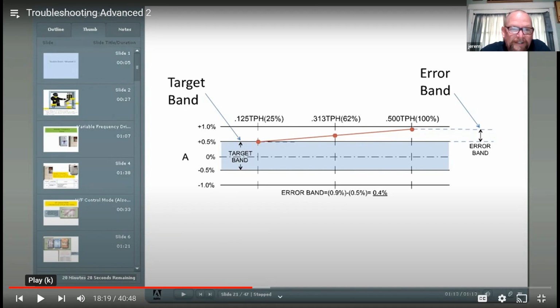Doesn't matter if you're minus 10% or plus 10%. If it's repeatable at either one of those, you can span it and get it to be right on the money that way. But if it's not repeatable, if it's bouncing from 2% minus to 4% positive back to 2%, back and forth all over the place, jumping around, there's nothing you can do. You've got to figure out mechanically where your issue is before you can try to span something of that nature.